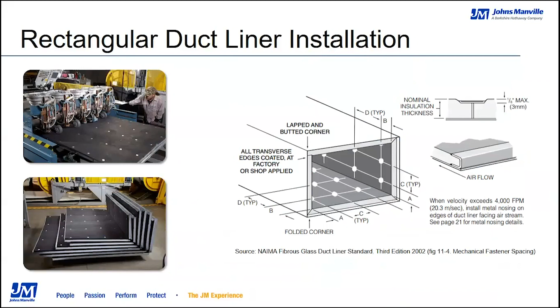If you look at the picture in the top left-hand corner, that gentleman is running a coil line—this is just a small section of it. The liner itself is moving from left to right, and what you're seeing is the pin spotter, where the duct liner, the black surface there, has been glued down to the piece of sheet metal. That pin spotter has mechanically fastened the duct liner to the sheet metal, and it's coming down the line, which will then be bent into an L shape, shown in the picture below. It's all stacked up, and those L sections are put together, shipped off, and installed at the job site. That's how duct liner is installed in a rectangular duct in the most basic sense.